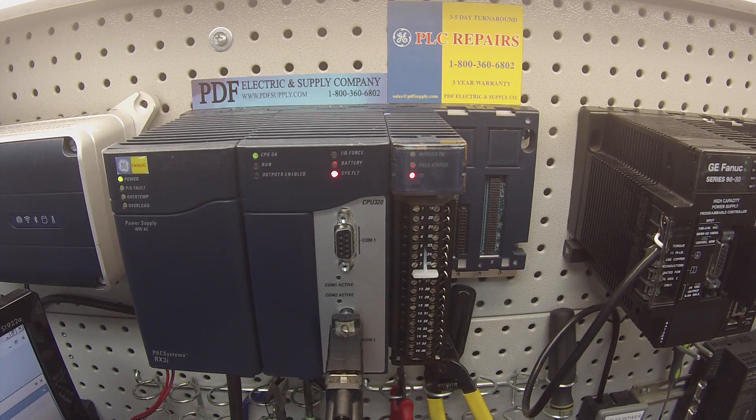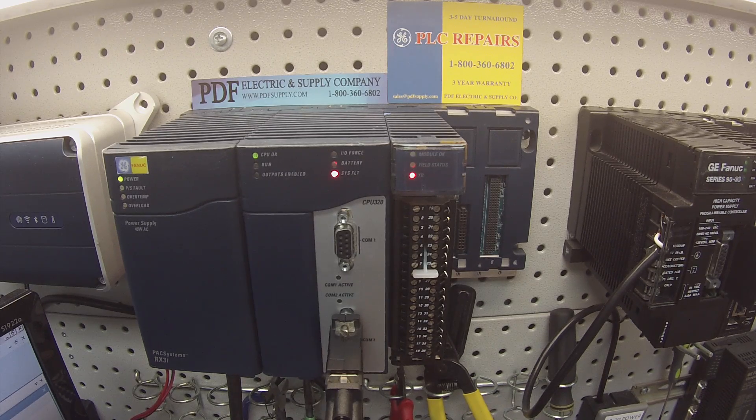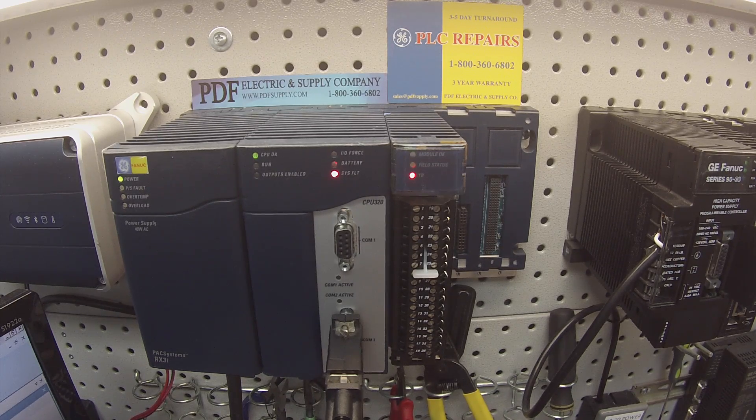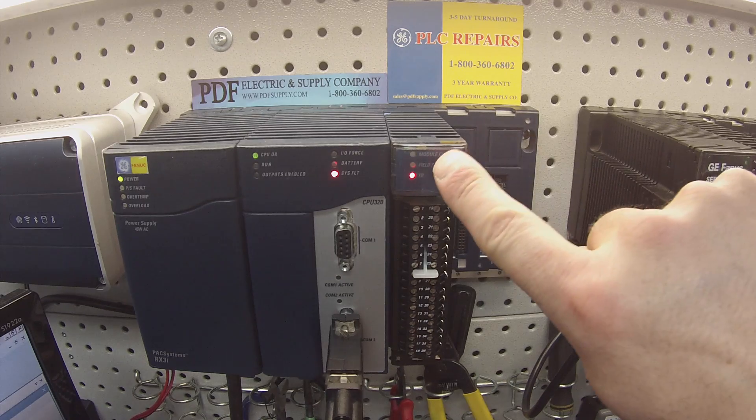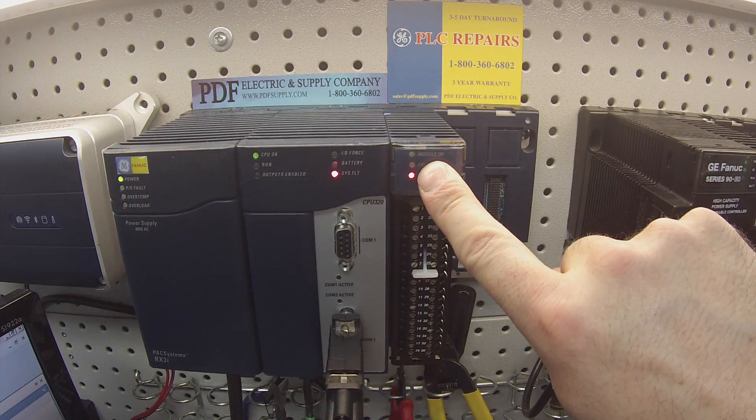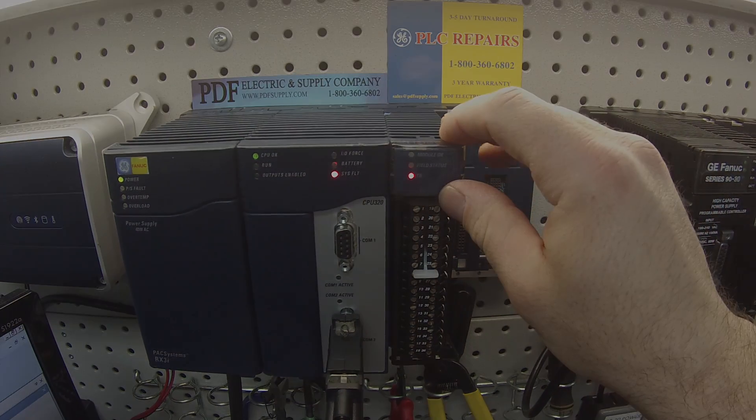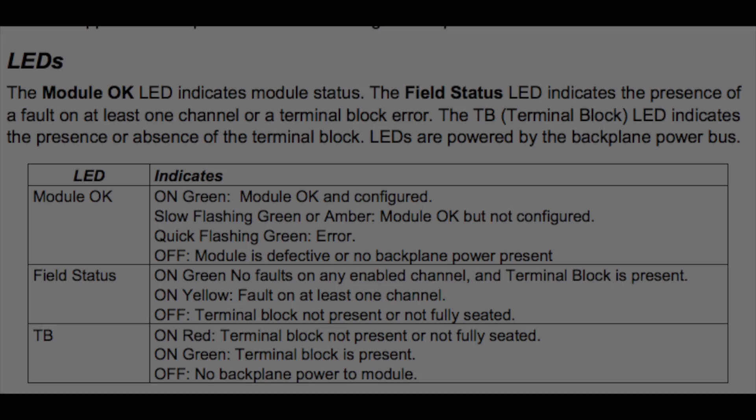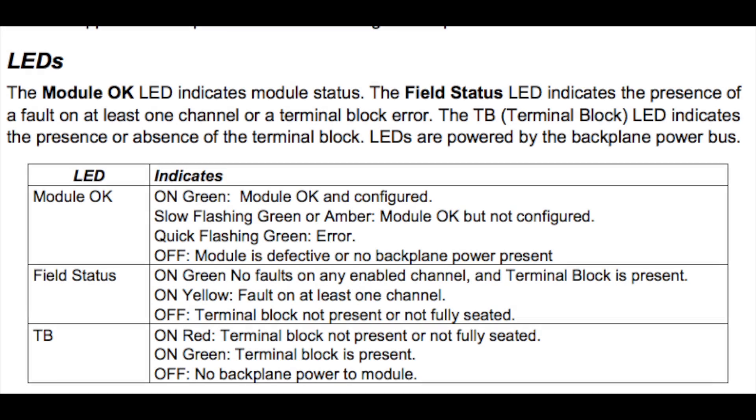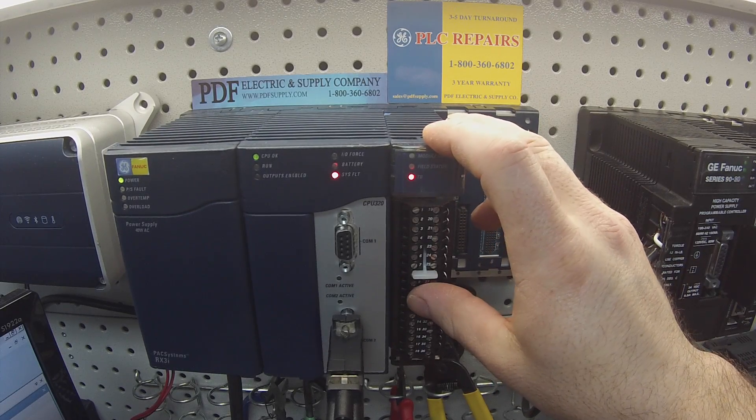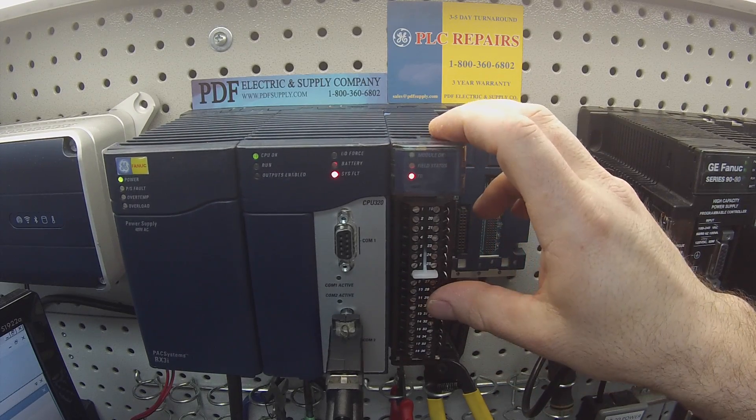First, if you notice I have the module in the rack that's powered up and I have a blinking green module OK light. That's a good thing to see. If you don't have any light on there or if it's red, then that means there's something wrong with the card that would need replacement or repair. It also means you wouldn't be able to follow this test. But if you have a system that's powered up the way you see it here in my rack, that's a good start.